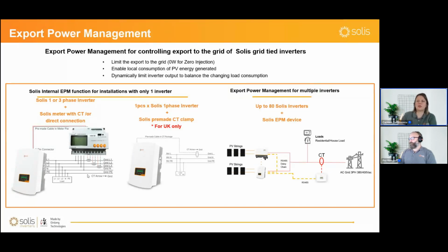Based on that, the inverter will use this information coming in from the meter to control its output, so that what we call backflow power, the value that you have set for maximum export to the grid, shall not be exceeded. It will adjust, not only try, but it will adjust its generation based on that value.